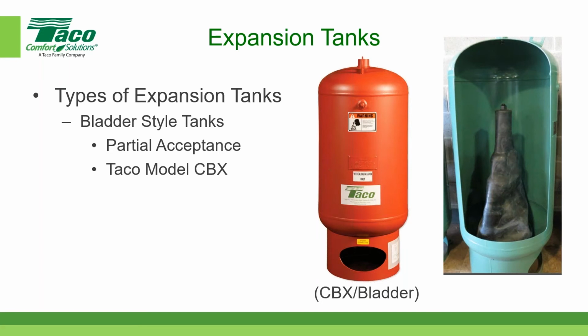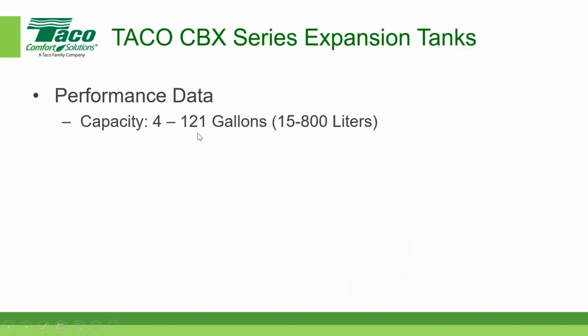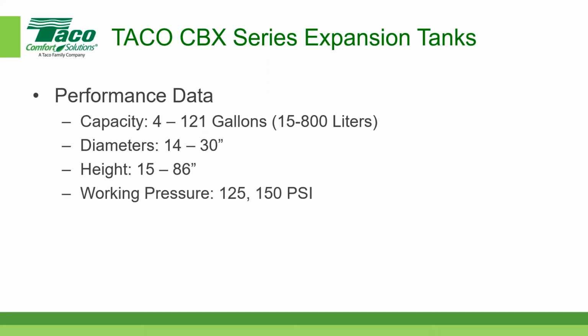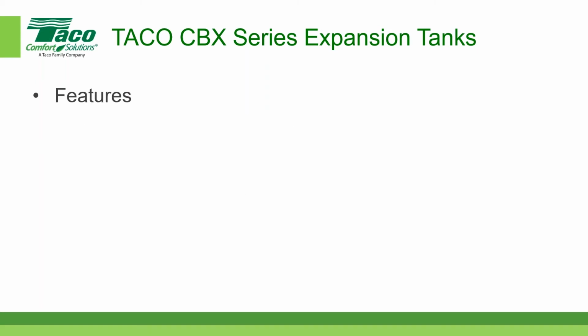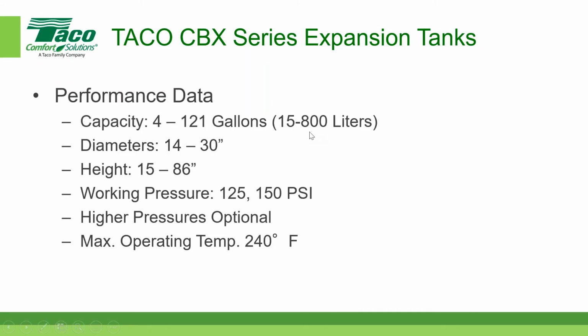So that's the difference between a full acceptance and a partial acceptance. But that is the TACO model CBX, a lot smaller, right? The other one was close to 4,000 gallons at its maximum. This one here only goes up to 121 gallons. So again, for smaller systems, right? You can see the diameters there. The other one was almost 24 feet. This one here is just over 7 feet high, with a lot lower working pressures. We can give you optional ones as well, it's just probably different welding. And the maximum temperature is 240.